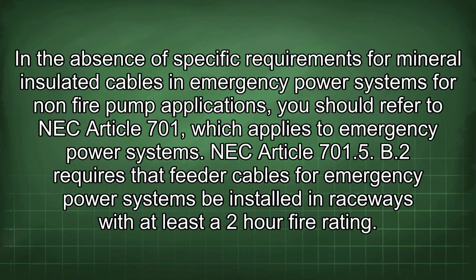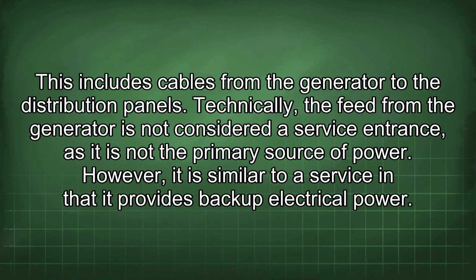In the absence of specific requirements for mineral-insulated cables in emergency power systems for non-fire pump applications, you should refer to NEC Article 701, which applies to emergency power systems. NEC Article 701.5 B2 requires that feeder cables for emergency power systems be installed in raceways with at least a 2-hour fire rating. This includes cables from the generator to the distribution panels.